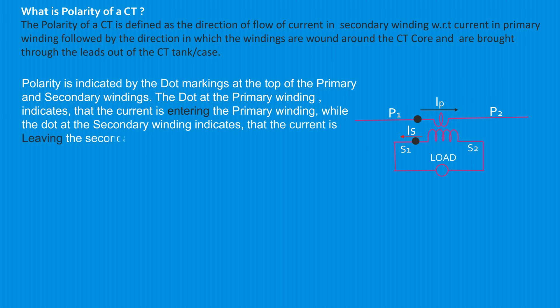The polarity marks on a CT designate the relative instantaneous directions of the current — that is, for a given direction of primary current entering, what should be the direction of secondary current leaving.